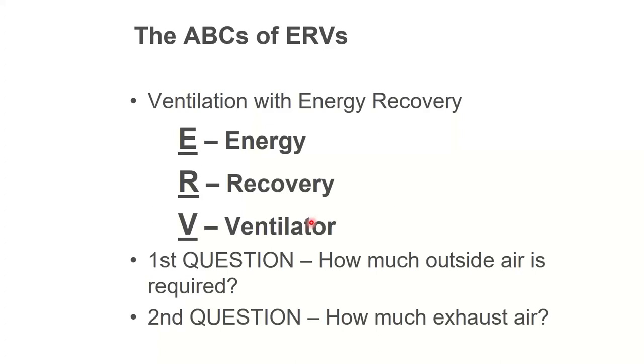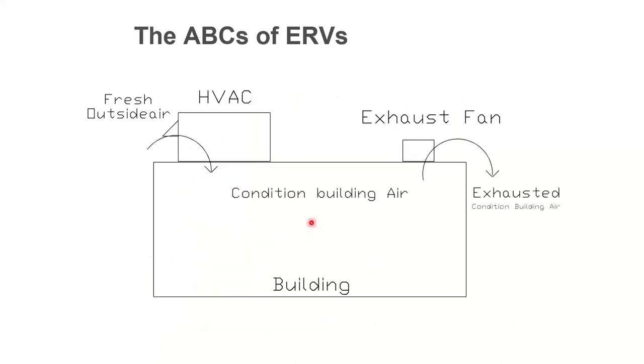Second question is, how much exhaust air do you have? Because I'm going to recover air, or not air, I'm going to recover energy out of the exhaust air and give that energy to the outside air. Well, if you don't have hardly any exhaust, who cares that there's a lot of outside air? You don't have any exhaust to get energy from, so what's the difference? Or vice versa. Great, you got a lot of exhaust where you're wasting all this heat. Well, I can't grab the heat and send it to the outside air because I don't have any outside air. So I need a lot of both for this to start making sense.